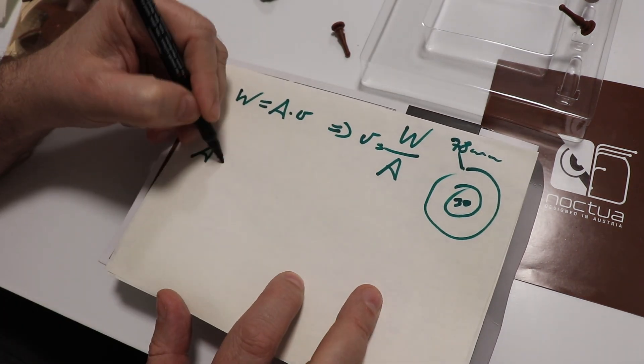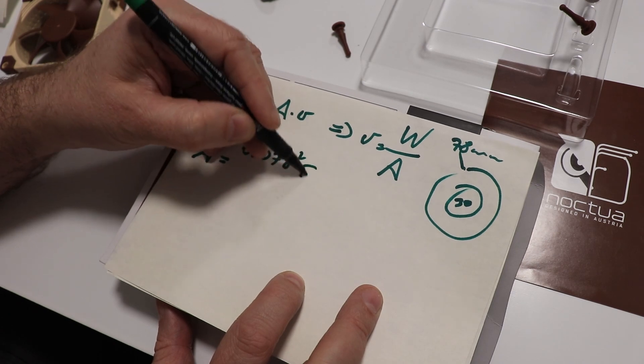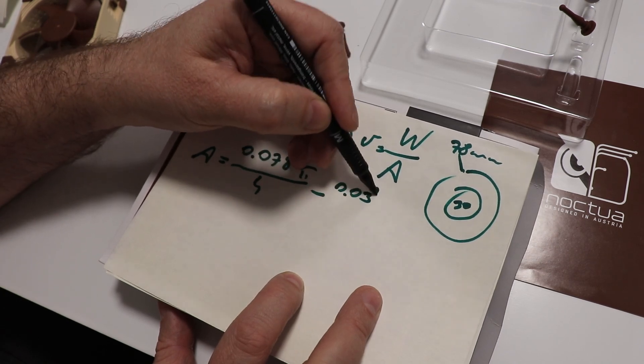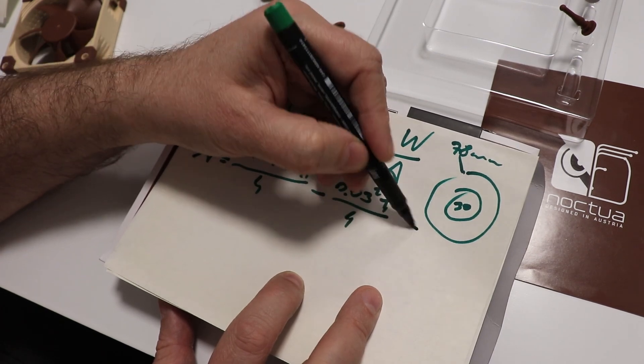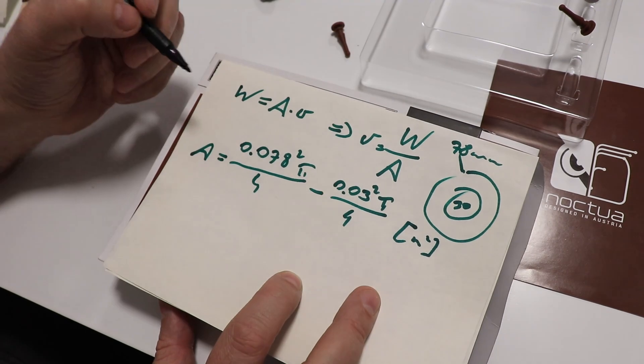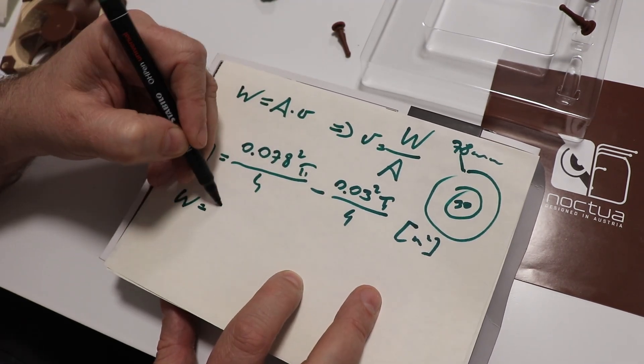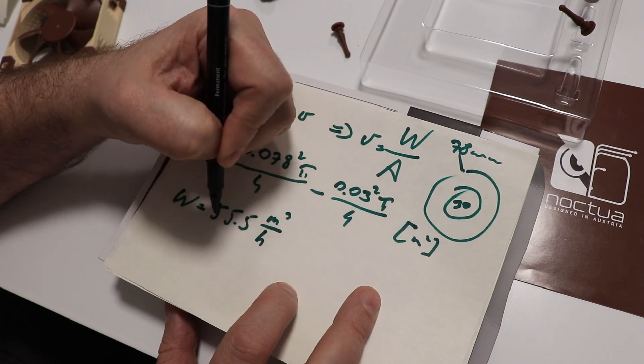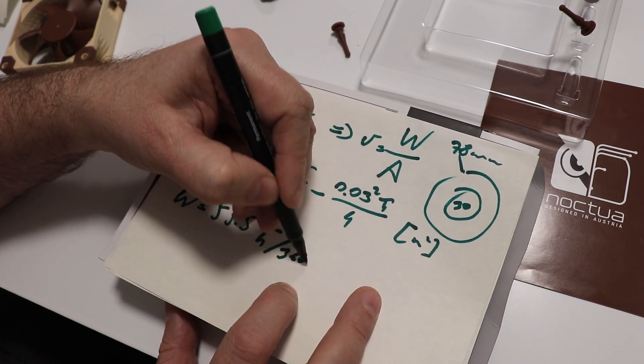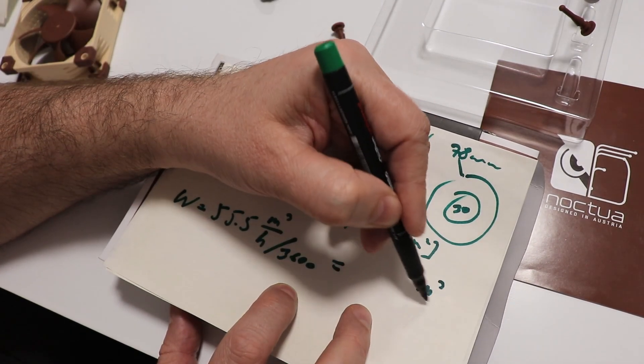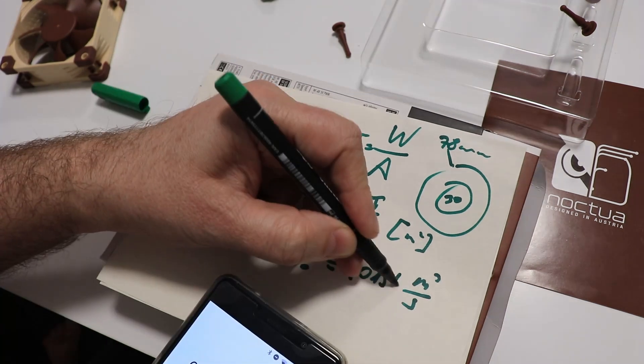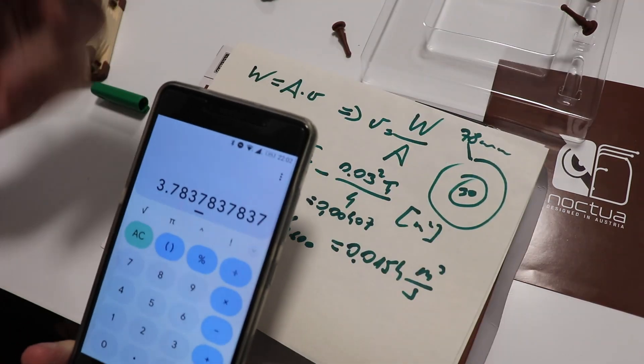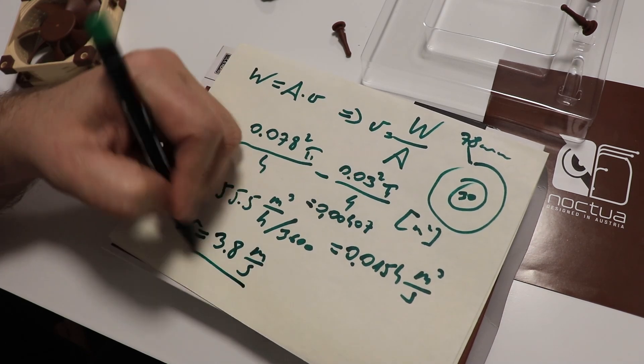So the area is 0.078 squared times pi divided by 4, and then subtract 0.03 squared times pi divided by 4. And this will be in square meters. And the flow rate I have to convert because it is 55.5 cubic meter divided by hours. And I have to divide this with 3600. In this case I will get cubic meters divided by seconds. The area is 0.00407, approximately 3.8.